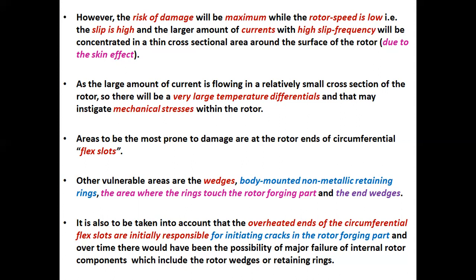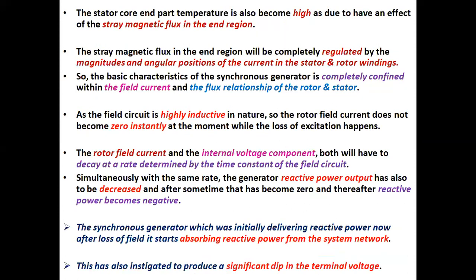Areas most prone to damage are at the rotor ends of circumferential flex slots. Other vulnerable areas are the wedges, body-mounted non-metallic retaining rings, the area where the rings touch the rotor forging part, and the end wedges. It is also to be taken into account that the overheated ends of the circumferential flex slots are initially responsible for initiating cracks in the rotor forging part, and over time there would be the possibility of major failure of internal rotor components, which include the rotor wedges or retaining rings. The stator core end part temperature also becomes high due to the effect of stray magnetic flux in the end region.